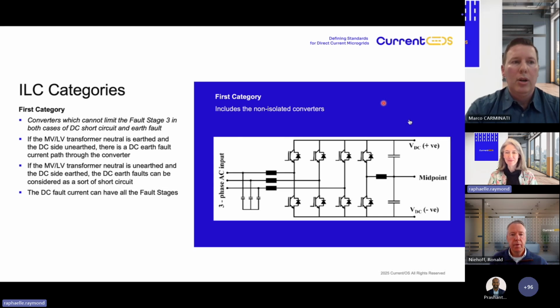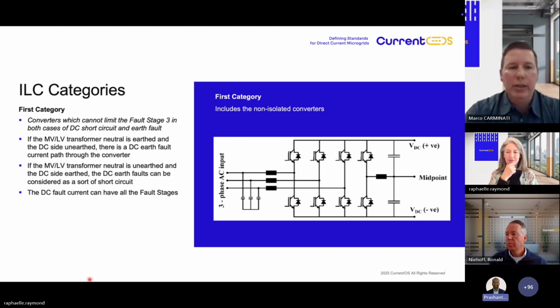All good. Yes. Okay. So if the medium voltage transformer neutral is unearthed and the DC side, usually the negative, is earthed, the DC earth fault can be considered as a sort of short circuit according to the fault resistance. I remind you that if we have a non-isolated converter, we cannot connect at the same time both the neutral of the medium voltage, low voltage AC transformer and either the positive or the negative on the DC side. Otherwise, we would have a permanent fault inside the converter.